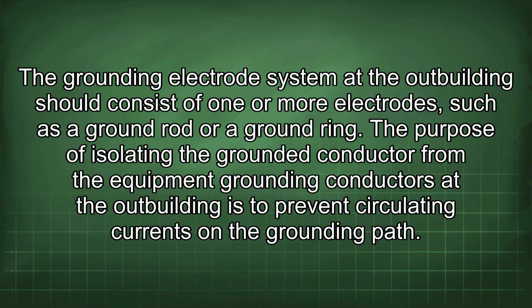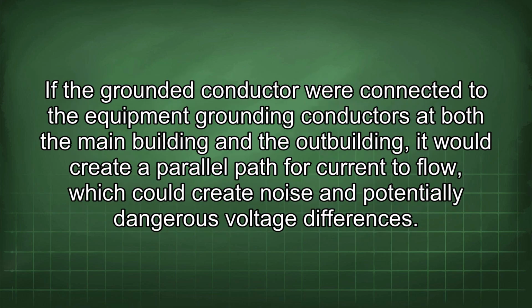The purpose of isolating the grounded conductor from the equipment grounding conductors at the outbuilding is to prevent circulating current on the grounding path. If the grounded conductor were connected to the equipment grounding conductors at both the main building and the outbuilding, it would create a parallel path for current to flow, which could create noise and potentially dangerous voltage differences.